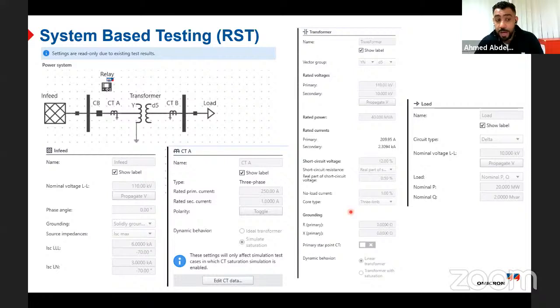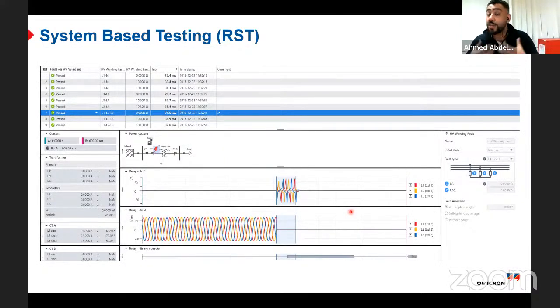To have what? To have the next slide, you are simulating a very close fault to one CT at the high voltage side, and at the end you can simulate a current transformer saturation and see if your system really responds correctly or not. Because the case which I faced a lot is that I go on site and I find a transformer, for example, protected with two different relay manufacturers, and finally I find that main one operated and main two operated. This is the confusion moment for any protection engineer.